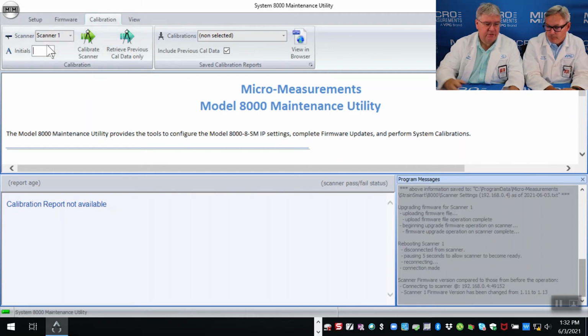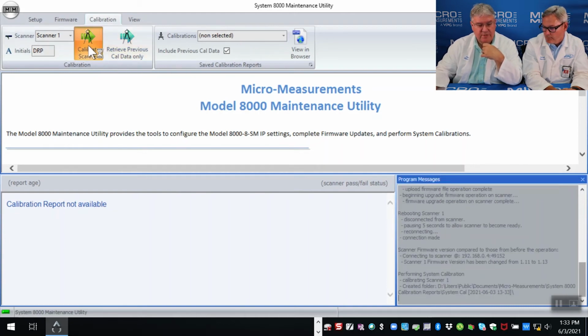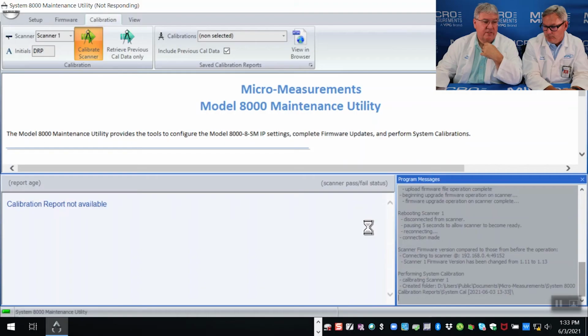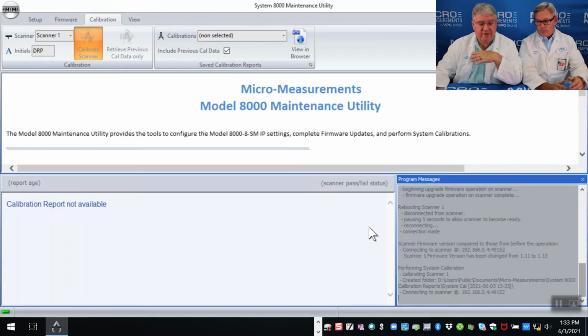So ready to do a calibration. We're just going to introduce some initials here. And since it's found the scanner and everything seems to be copacetic with it, I'm going to tell it to go ahead and calibrate the scanner so I have something to talk about here, because it'll take just a second, do those voltage injections, do those voltage measurements, and then it's going to wind up reporting back what the final result is. There's actually 5 different steps, 5 different stages in which it's getting evaluated.